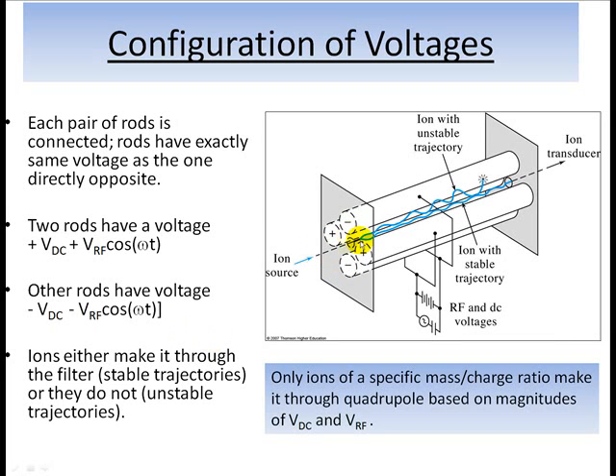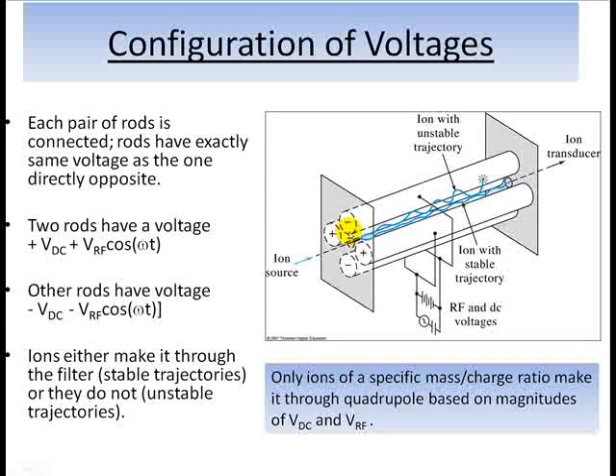Ions, as they're going down through this central area within the quadrupole, they're affected by the fields because, of course, the ions have a positive charge on them. In any given time, if the ions are sensing a negative field, they'll be attracted in that direction towards that field.